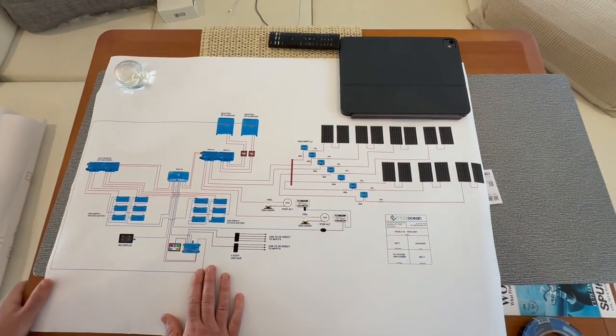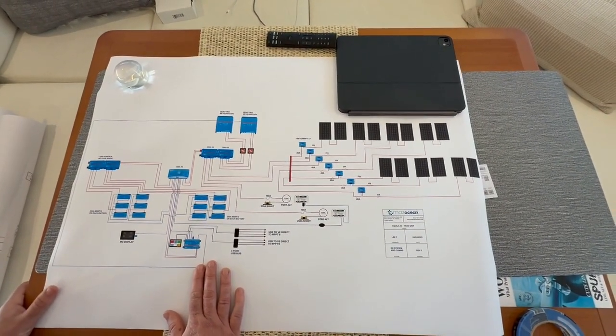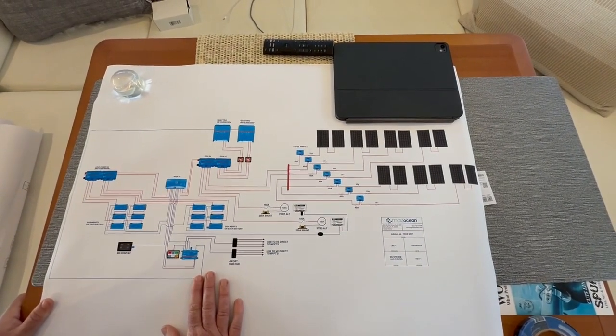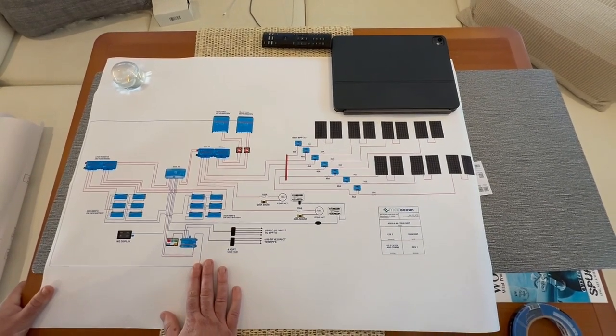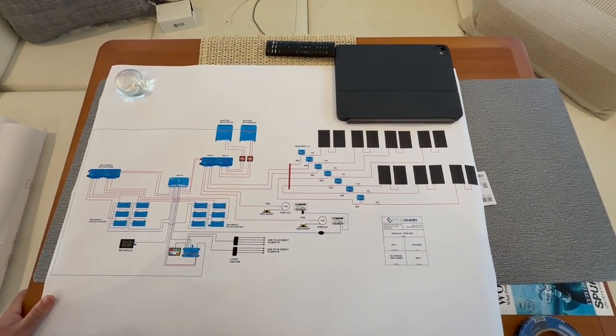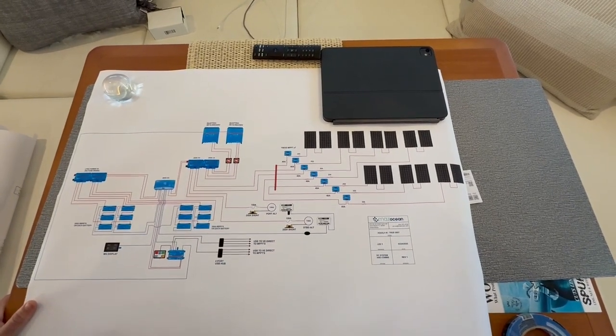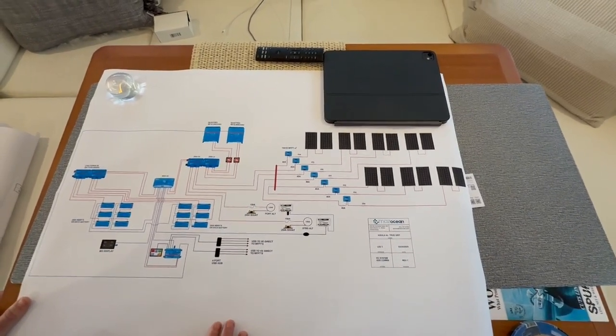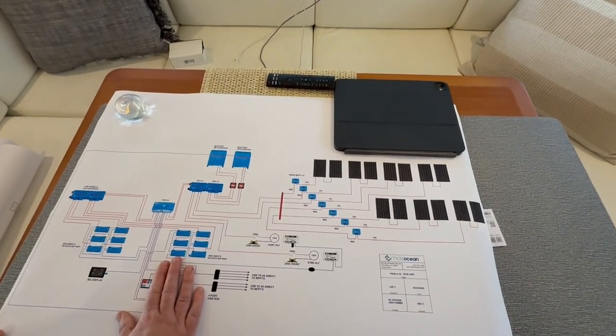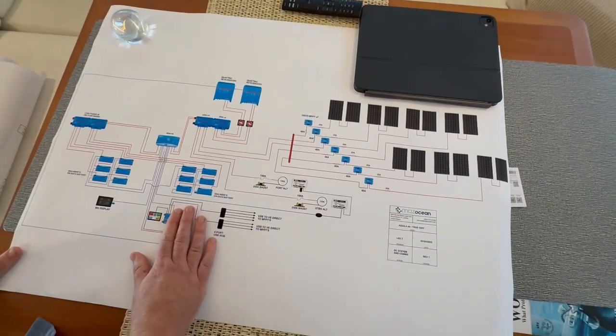Those were 24 volt batteries that we wired together in pairs, in series, to create a 48 volt system. There are six of those pairs, 12 batteries total, for 86 kWh - 86,000 watt hours worth of battery capacity. To be honest, it's probably the biggest battery bank we've installed to date, or very close to one of the largest, giving Curtis the ability to really be off grid.